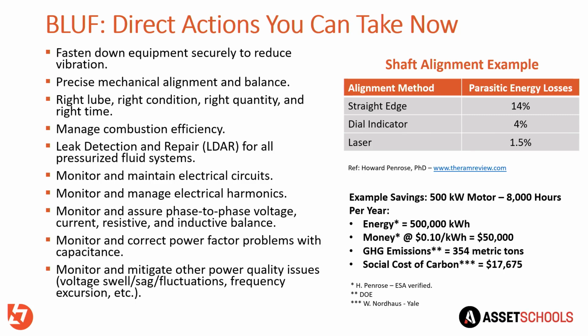Now, I was talking to some of our electrical engineers, so we have smelting operations in our platinum group metals. And I said, do you think we have any current on our ground and neutral? One of the electrical engineers said, yeah, the safety rails are hot. We've got current flowing. There's a lot of nonlinearity in a smelter because these are electrical, all single phase, a lot of problems there. So yeah, I'm seeing that. So take a look at your ground and neutrals, and if you are seeing any amperage at all, that current is going back to your transformer, and that's where the problems occur.